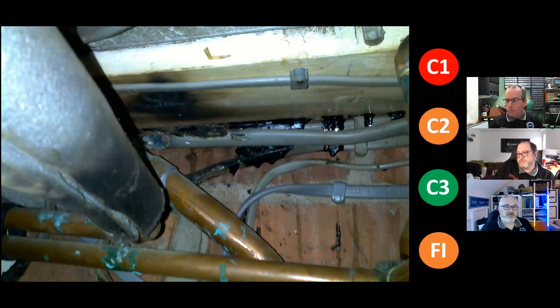I'm playing devil's advocate here while you guys are doing your thing. I can't see exposed copper, and that would be a C1, danger present. Definitely it's potentially dangerous, urgent remedial action, because the cable's been subjected to thermal issues. It needs ripping out, rewiring and replacing. But is there an immediate danger, given that it's placed out of reach? It's not accessible, so if there is any damaged insulation, it's not readily exposed and live. Would there be any need to do further tests or inspections to understand this risk more, or is visual adequate, do you think?